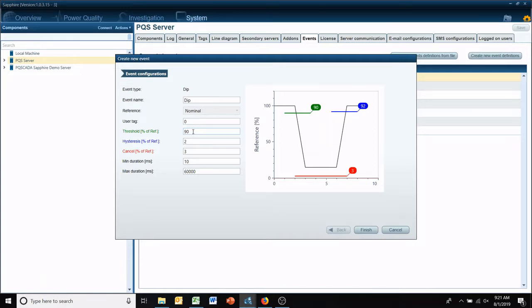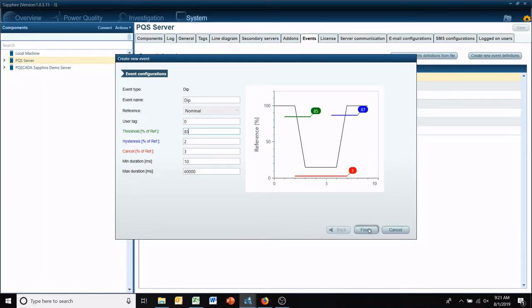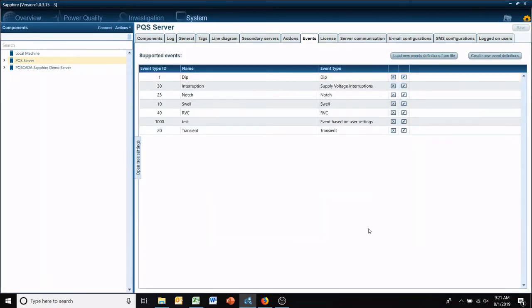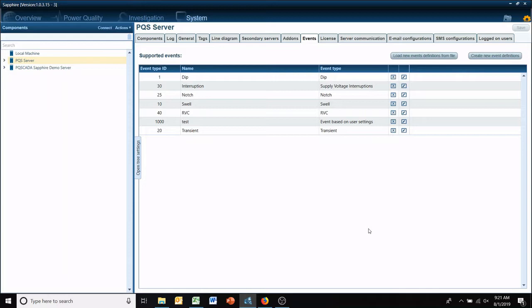Right now it's set to detect a 90 percent sag, or 10 percent below nominal. So we could change that to 85 and then finish. So now any events that are generated by the PQ server will have a threshold of 85 percent.